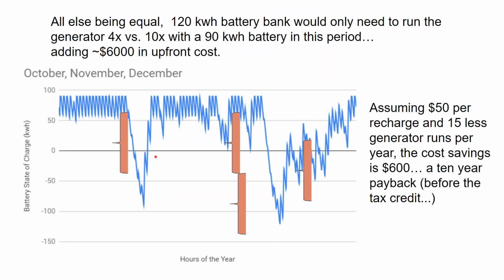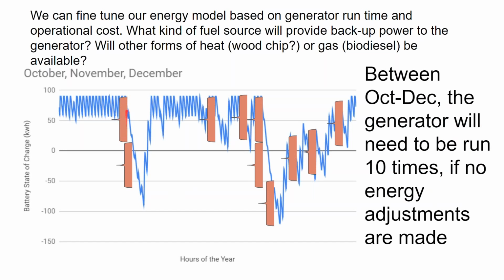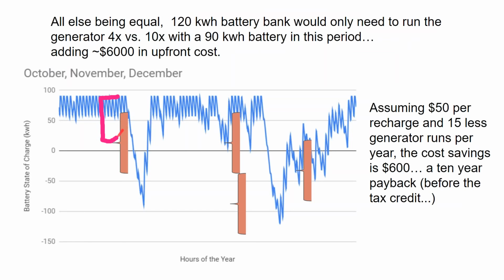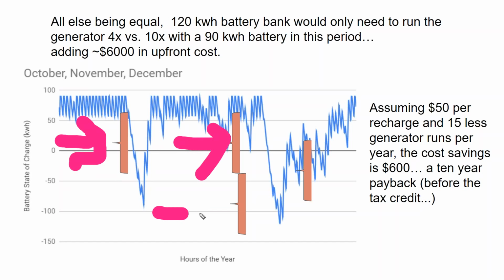So I would look at this and say, okay, what if instead of doing a 90 kilowatt hour battery bank, represented by something that is yay big, what if I did a 120 kilowatt hour battery bank and had a little more range out of my system compared to 90 kilowatt hours? So I have 30% more because I go with a 30% larger battery bank. Well, in this exact same weather pattern, I would only need to crank the generator once, twice, three, four times instead of ten times.